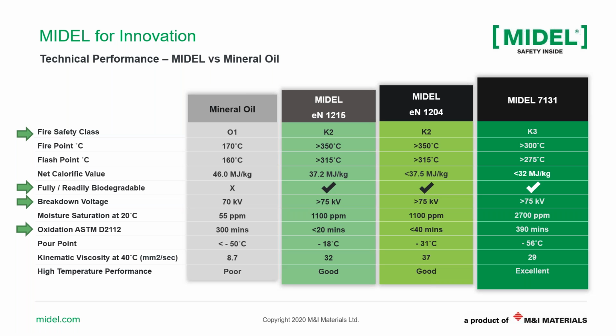And also mineral oil has a lot of energy in it. It has high net calorific value, more than 46 megajoule per kilogram, meaning when it burns, it will release a lot of energy. Now, esters have different story. They are classified as K-class fluids. The reason being they have fire point higher than 300 degrees. MIDEL EN are the natural esters. They have typically fire point higher than 350 degrees, while MIDEL 7131 is the synthetic ester, has a fire point typically higher than 300 degrees. So this is the first one, is the fire point, and this really contributes how you space your transformers from one another in a substation, or the need for fire suppression system. All depends on your risk assessment and insurance policy.